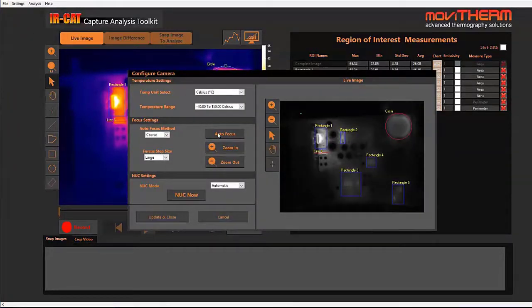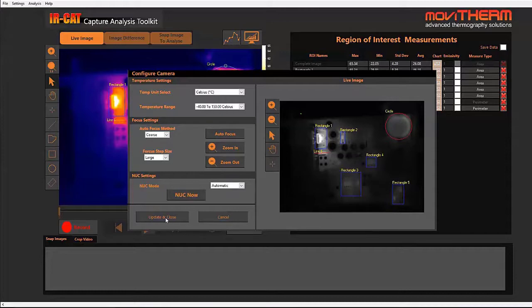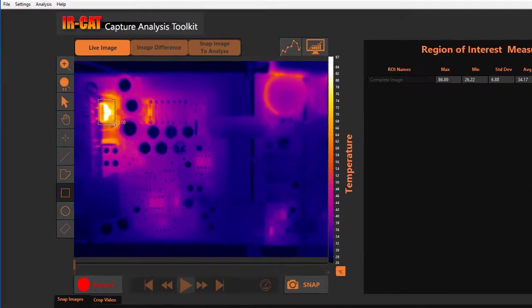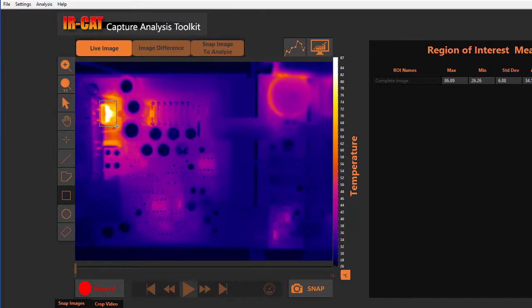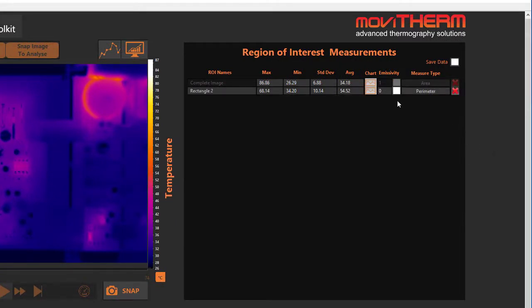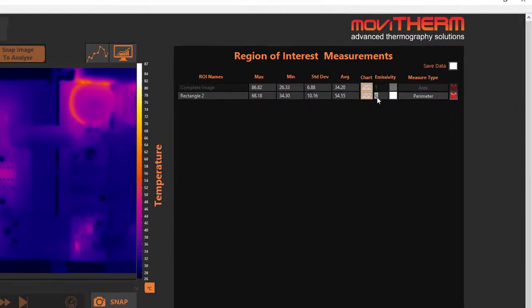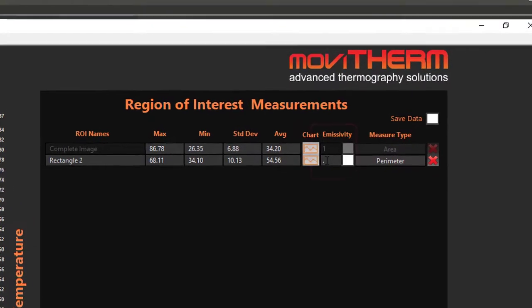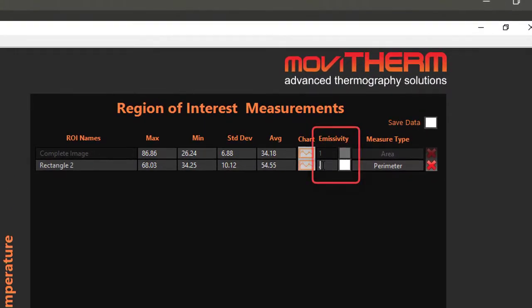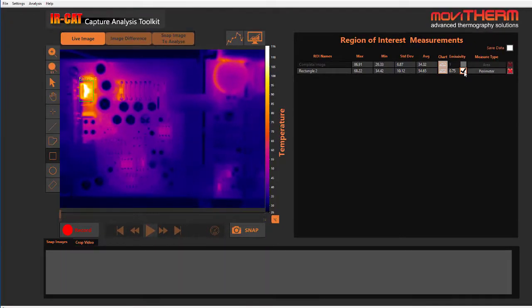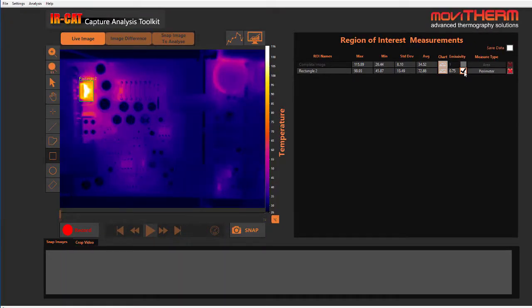The software includes several unique and advanced features for research and development tasks. For example, local emissivity corrections permit you to match the emissivity characteristics of different target materials in your inspection image. That way the temperature readings will be reliable whether you are inspecting a homogeneous object made of a single material or an object composed of several different source materials.